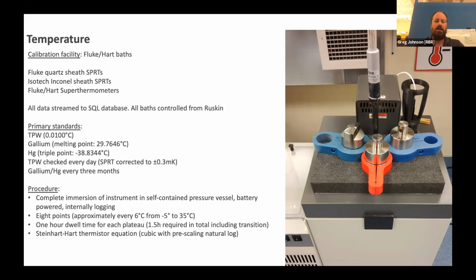And we actually check our SPRTs against the triple point every day. And if the SPRTs drift, as they have a habit of doing over time, then once they reach about 0.3 millidegrees off of 0.01, then we correct them again. We do the checks against gallium and mercury every 3 months. They're a bit more laborious, and we don't typically find that there's anything that wasn't found by the SPRT that gets found by the gallium or mercury. So that's really what we're doing, and then doing a fit to those 8 points and that cubic. So you can see that's got sufficient number of points to make a good fit, and assess the residuals. And that is generally the behavior of how we do temperature calibration.